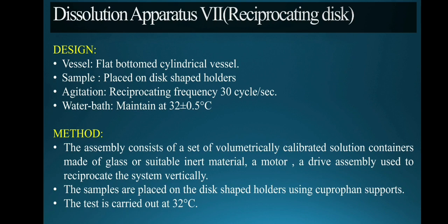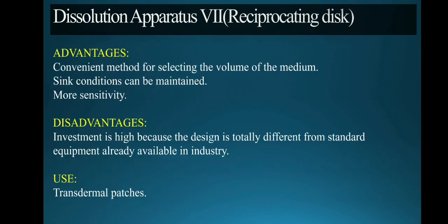The samples are placed on the disc holders using Cuprophan supports, and the test is again carried out at 32 degrees Celsius. The advantages include that it is the most convenient method for the dissolution of the medium, its sink conditions are always maintained, and it has more sensitivity than other apparatus. Its disadvantages are that the investment is high because the design is totally different from the standard apparatus and they are mostly used for transdermal patches.